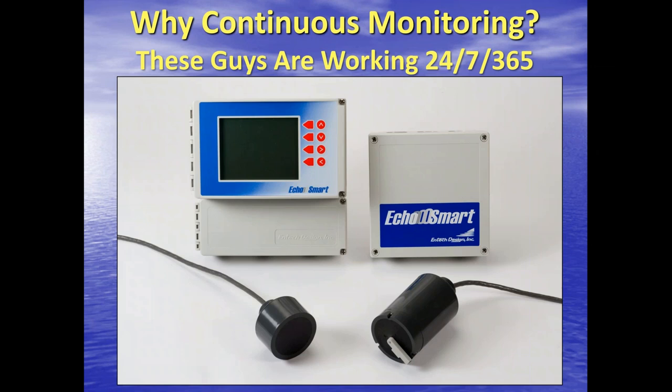Now we have three sensors in our line. The one on the bottom left here is about the size of a hockey puck. And notice that it doesn't have a wiper like the one on the right does. The one on the right is what we call a wiper or self-cleaning sensor. And here's an important point. With underwater ultrasonics, you always have to have a way to keep bubbles or gas off the face of the sensor.